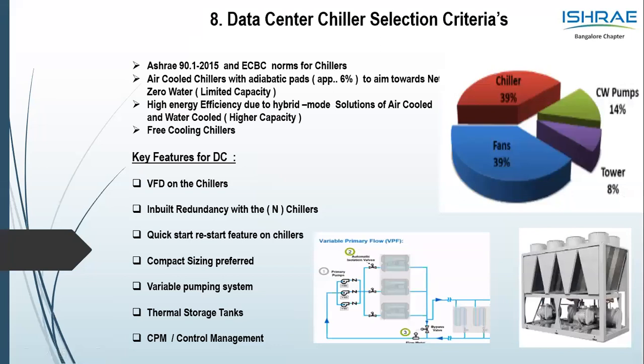As we get into the hyperscale data center, chillers go into a larger data center. Thanks to a couple of my friends from the industry, they've shared a good note on the chiller. Number one is that you refer back to the ASHRAE 90.1-2015 to check on the best COP on the chiller. Any DC space where you have a chiller, a pump and a fan, the major chunk of the power consumption comes from the chiller. So the right design of the chiller is very important.